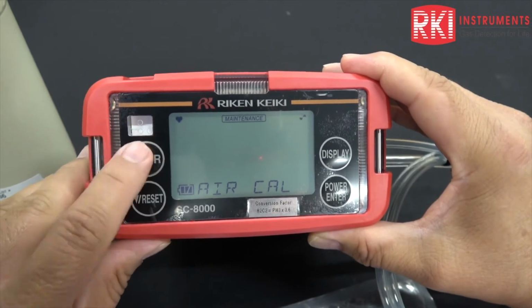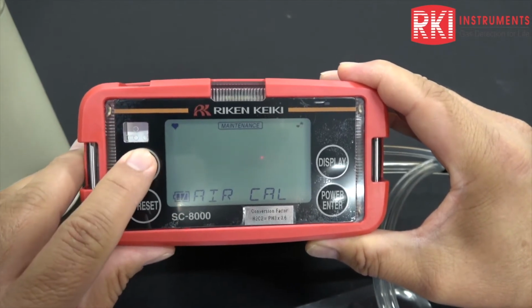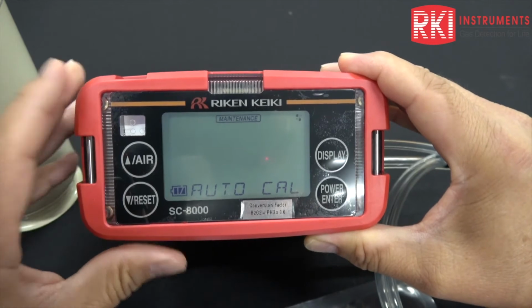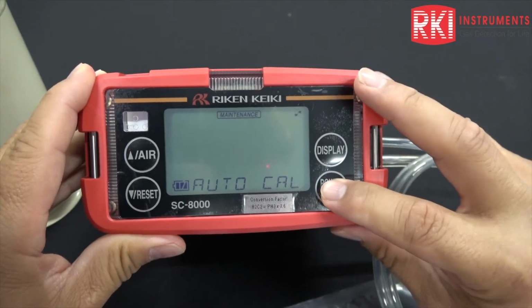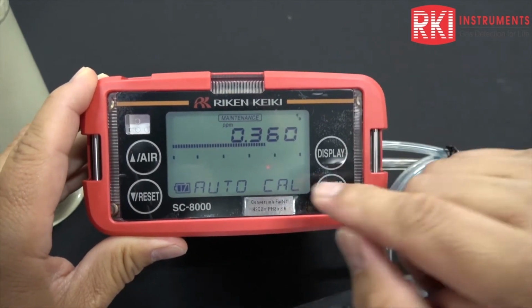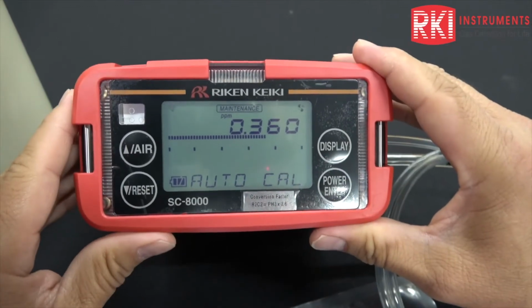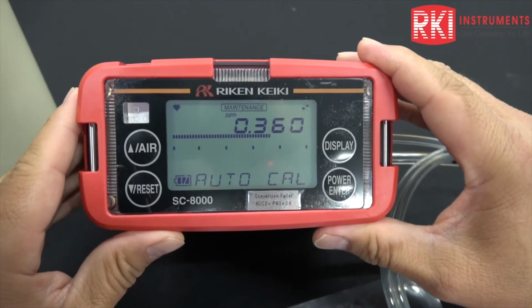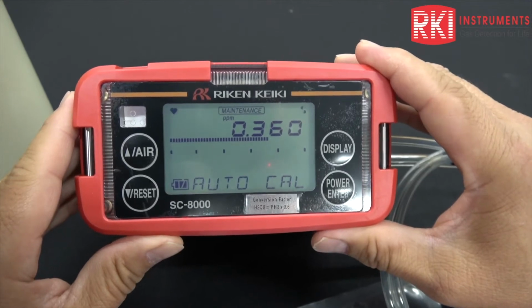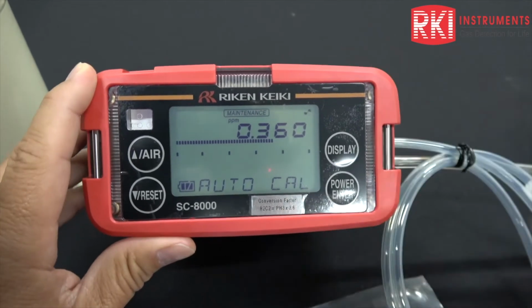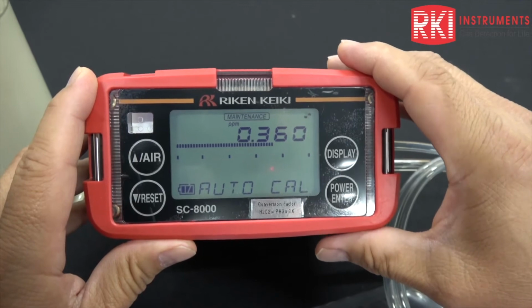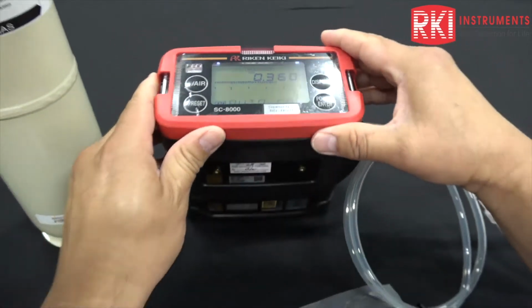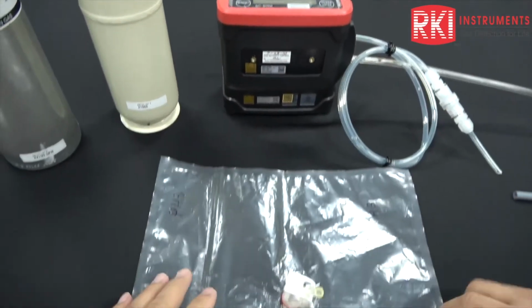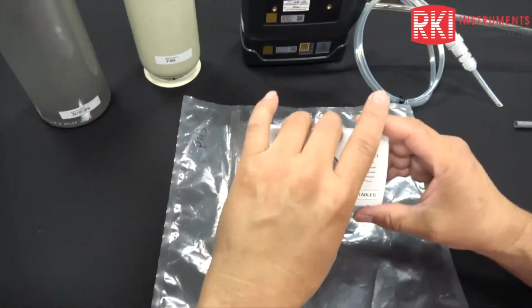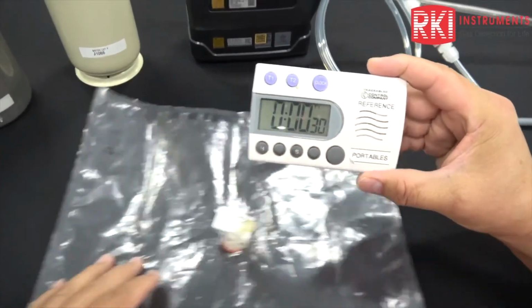Now I'm going to press the up arrow key, or the air button, up just one button, push. That will bring us to auto cal, and then press the power enter button to get into auto cal. And then you can see, as I mentioned, 0.360 ppm is equal to 360 ppb. So you can look at it either way you want. They're equivalent values. Okay, so the unit's ready itself. So now we need to put the gas into the bag. So I've got the setting here at 30 seconds. So once again, we're going to flow the gas into the bag.